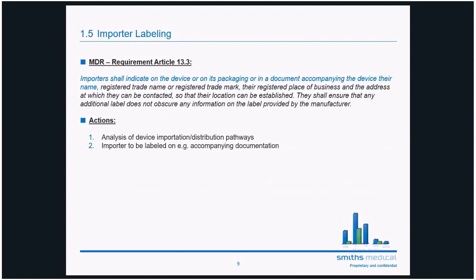Right, a very simple and straightforward requirement from MDR Article 13. The importer is basically to be listed, and the MDR gives a various set of options. It can be on the device, it can be on the packaging, or in documents accompanying the device. As the MDR is giving a set of options here, the manufacturer can choose. As part of harmonization and the work that we have done in the labeling working group, we have come to the conclusion that a good option is to place it in the documents accompanying the device.